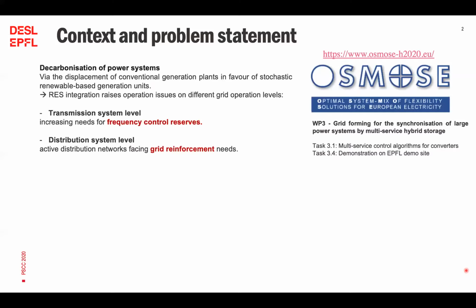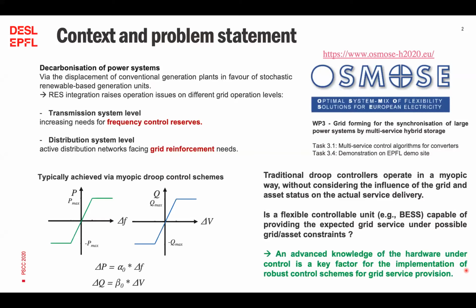Within this framework, the H2020 European project OSMOSE aims at investigating the option of exploiting controllable resources such as battery systems in order to provide multiple ancillary services at the same time, simultaneously. In this work, we have been focusing on the provision of primary frequency control and voltage magnitude control, which traditionally are achieved via myopic droop controllers that operate in a myopic way, thus without considering the influence of the grid and asset statuses at the point of the actual service delivery.